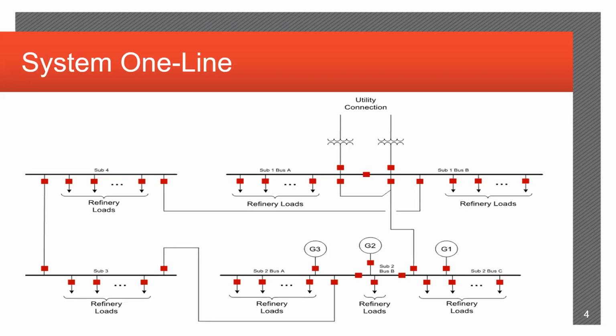Here's a picture of the system single line diagram, and I'm hoping everybody can see my mouse. So I'm going to point around with it a little bit. Up here on the right is a 46 kV connection to the local utility, a pair of step-down transformers that goes down to this main power distribution center here. Everything below these two transformers is 4 kV. And as you can see, each one of these power distribution centers has refinery loads connected to them. And then there's a big loop that goes from the main PDC, has a tie line down to the power plant. And that's where the 3 steam turbine generators are.